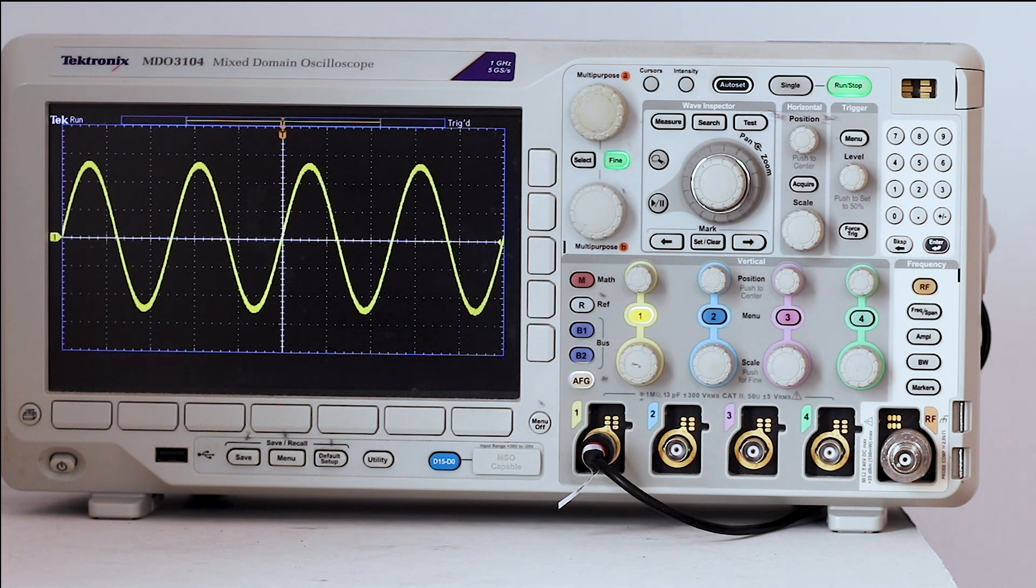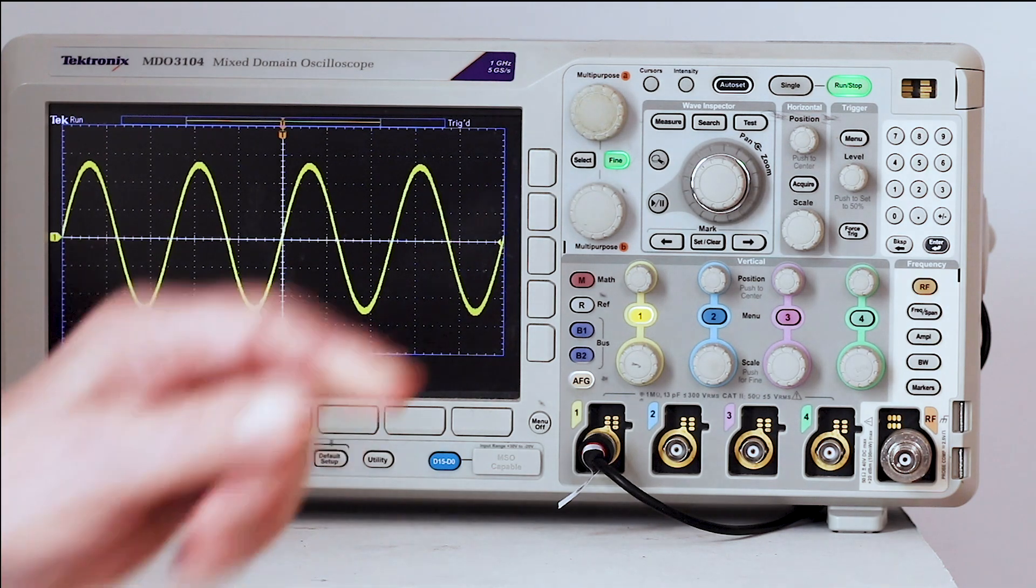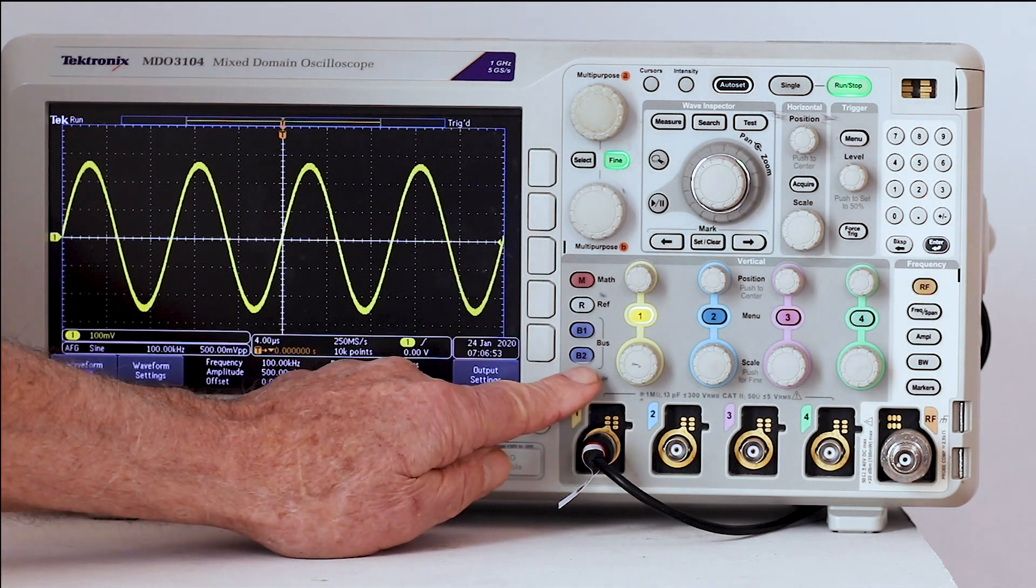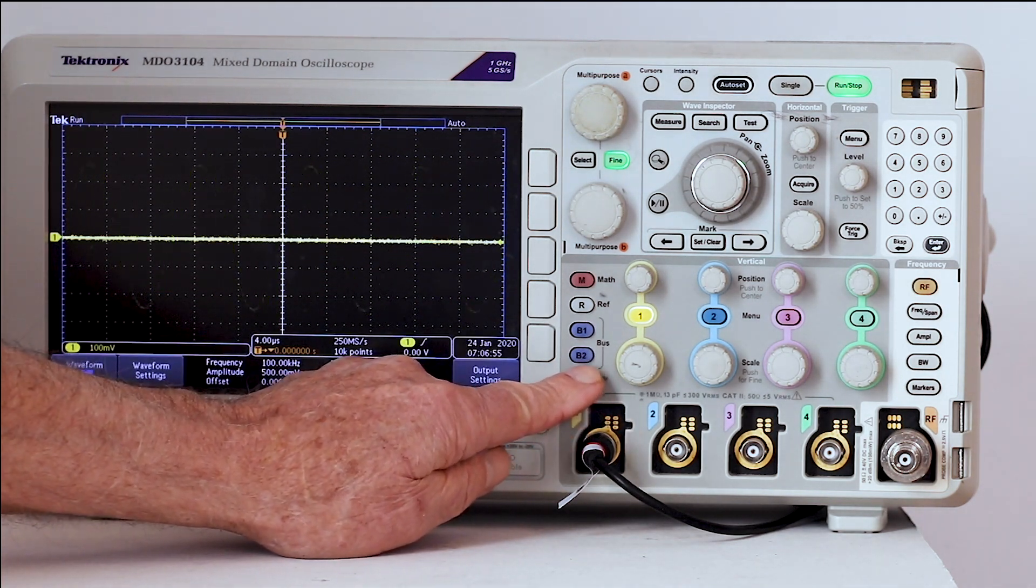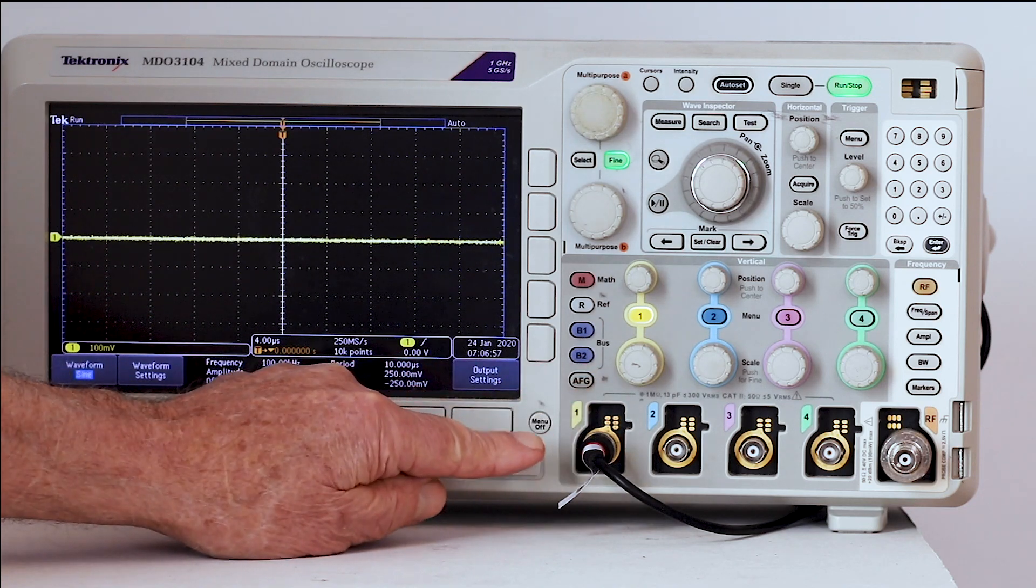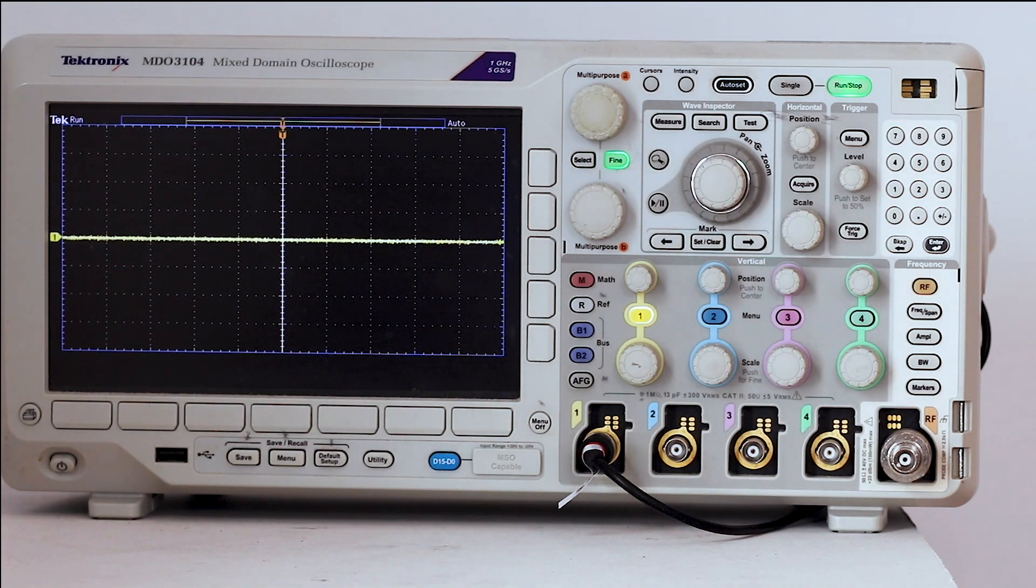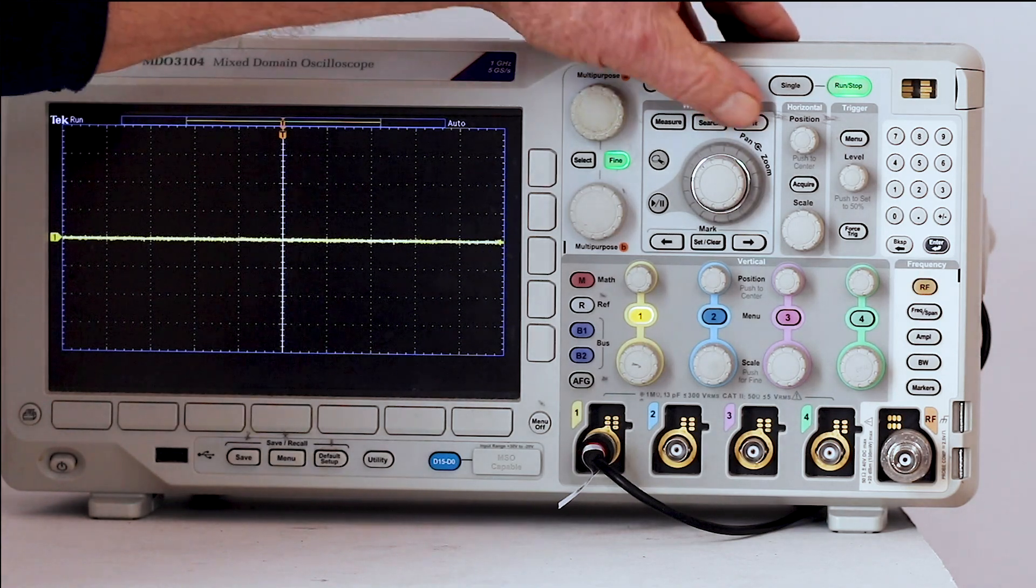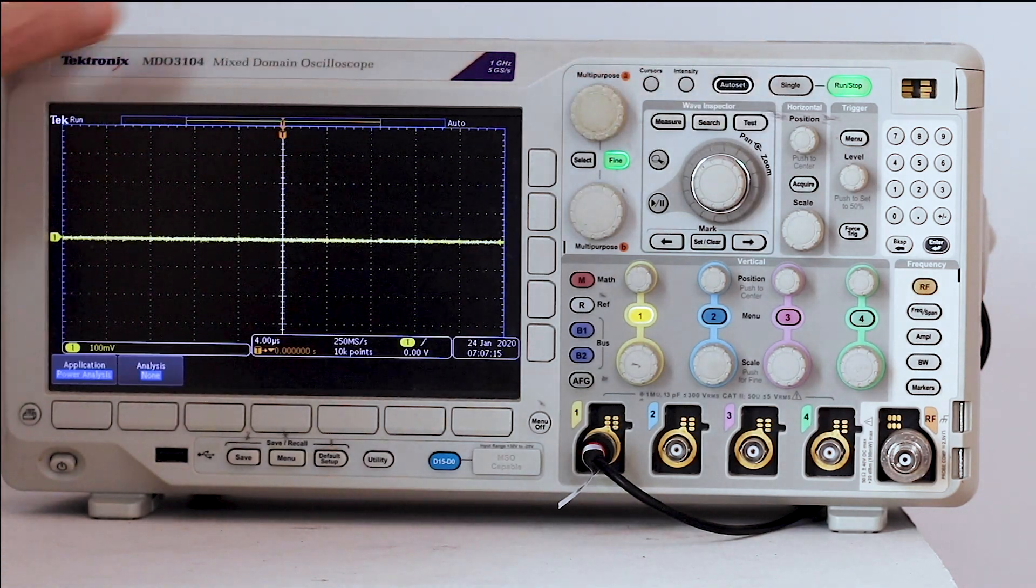To begin, with the oscilloscope powered on, press menu off and default setup. Now the instrument is a blank slate with the irrelevant settings removed. In the wave inspector section, press the test button and application.